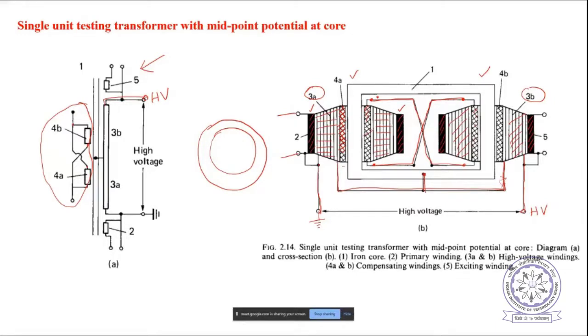Now, one thing: the compensating windings are physically not connected to any of the terminals of the high voltage, excitation, or primary windings. This is independent actually. Both compensating windings are only connected among themselves, such that a dotted terminal goes to a dotted terminal. Other than this, they are not connected to any other winding — not to primary, not to exciting winding, not to high voltage winding, physically.